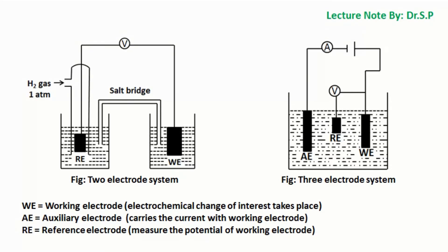In the two-electrode system, current passes between the working electrode and the reference electrode, so polarization of the reference electrode takes place. But in the three-electrode system, current flows between the working electrode and the auxiliary or counter electrode, so there is no polarization of the reference electrode.